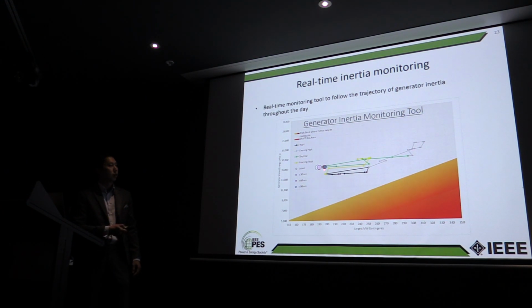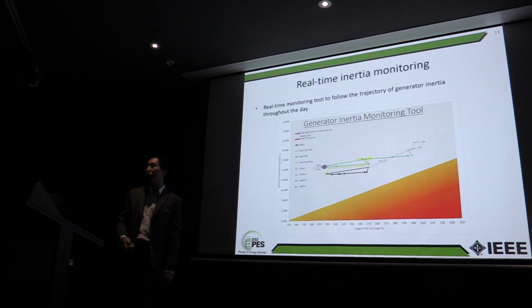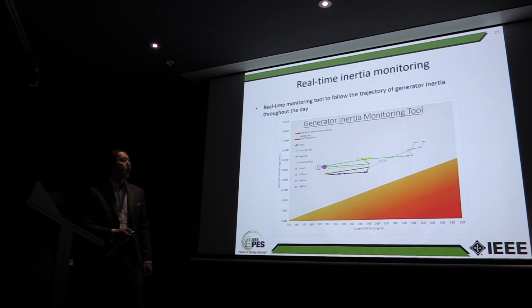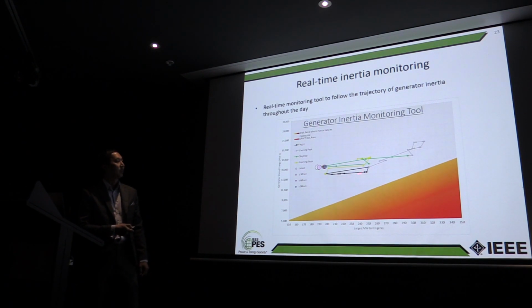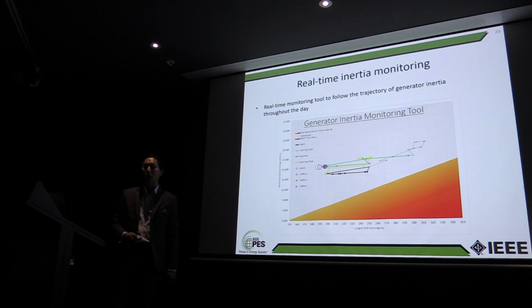So these big bubbles here are where the inertia is at right now. And this is a trajectory over the last day. The green ones are during the daytime periods, the yellows in the morning, and this is sort of evening peak and night. As you can expect, evening peak is when you have the most inertia because you have most of the generation on during the evening peaks. And it's really at night, this time here, where you have the lowest amount of inertia, and sometimes during the day as well, when we have a lot of solar penetration.